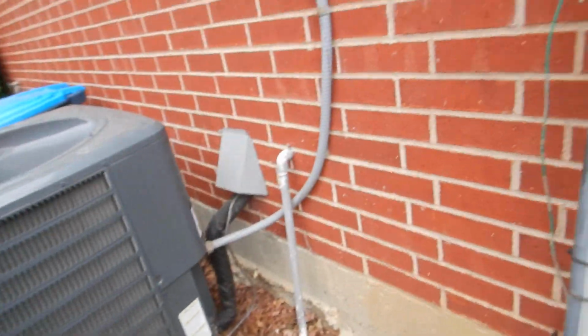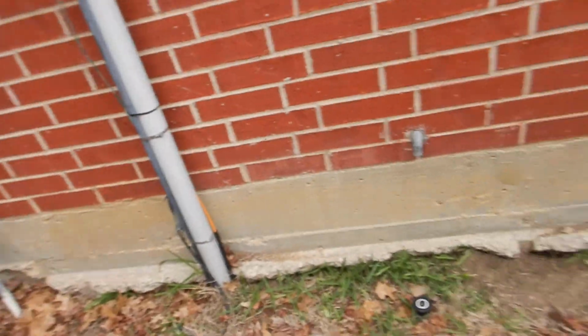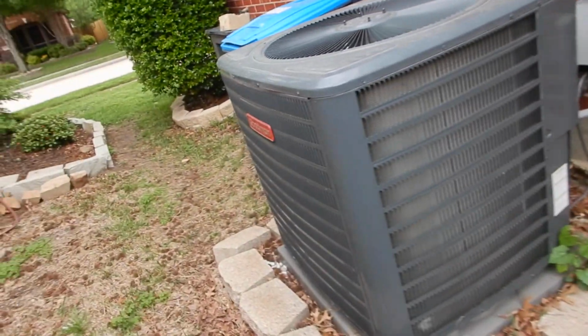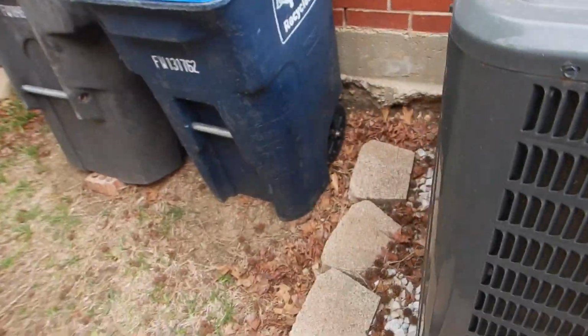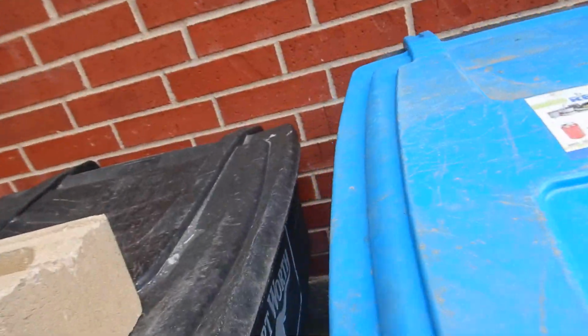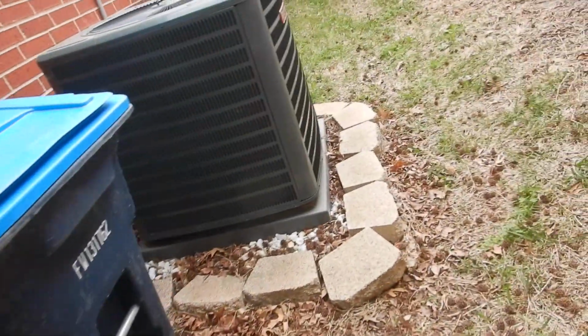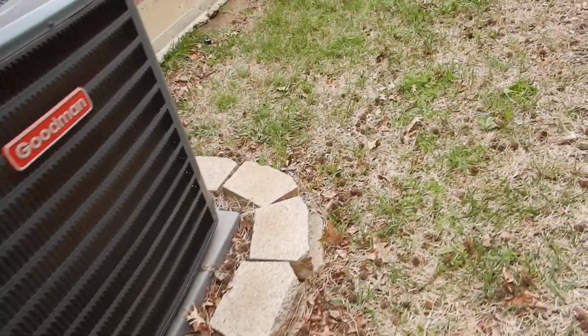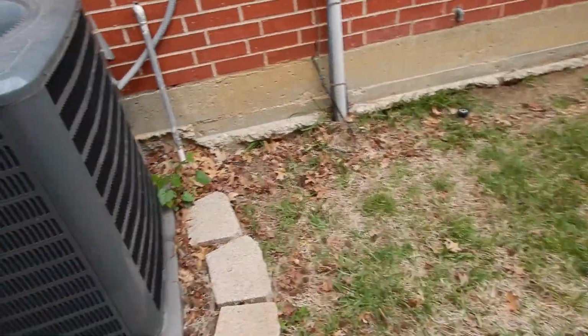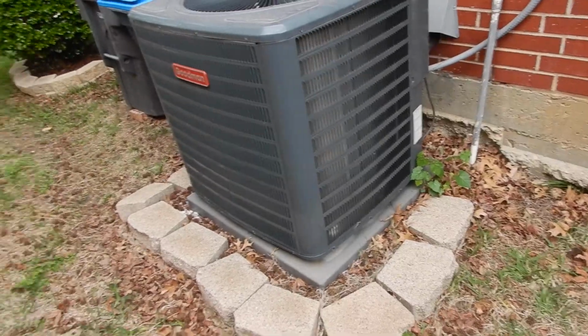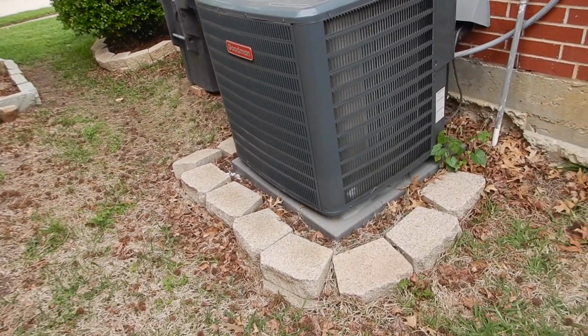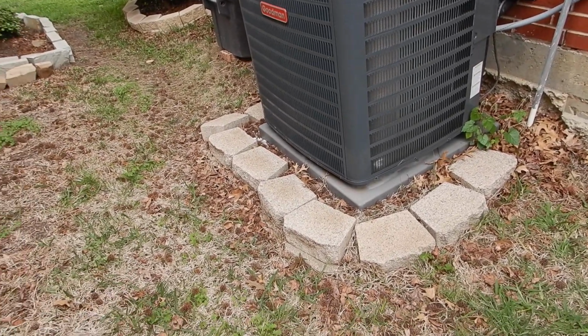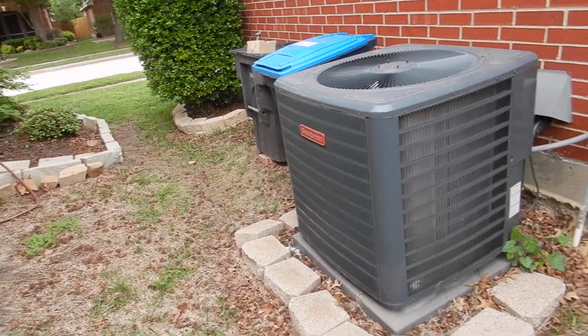So what did we learn? Our disconnect was not properly sealed. We also learned that we do not have an electric receptacle outlet out here, a service outlet. Is that true? It's not looking like it. Okay, we do not have an electric receptacle outlet out here, so the technician can hook up a vacuum pump or any kind of electrical equipment like that, even a light, a luminaire in the middle of the night, so you can work on your equipment. So we're missing our electric service receptacle.